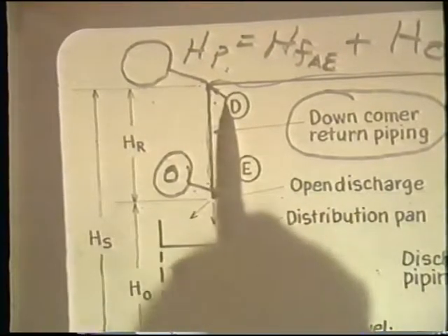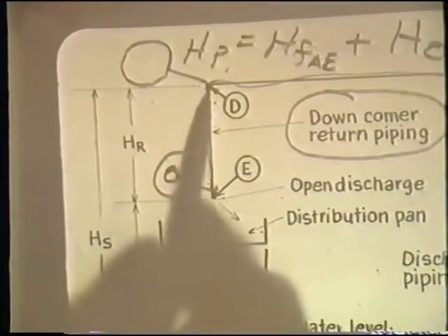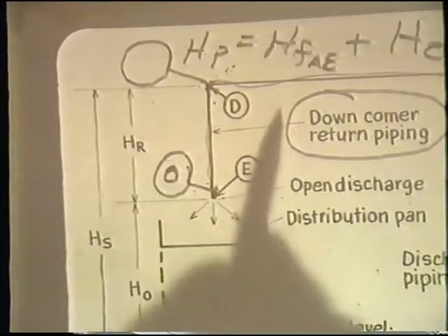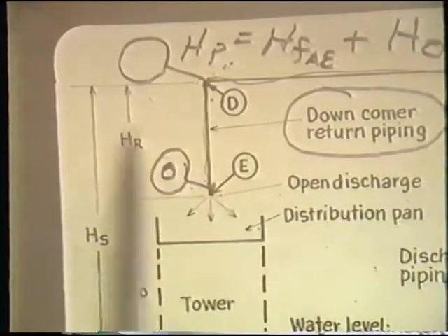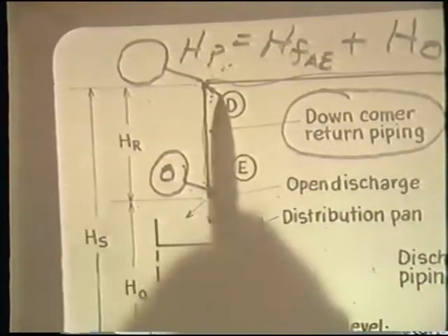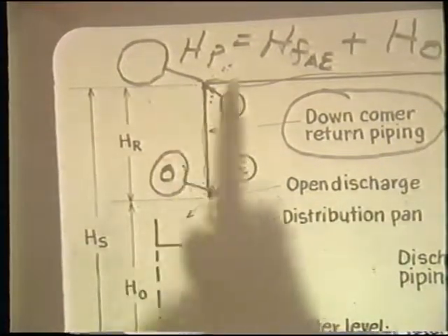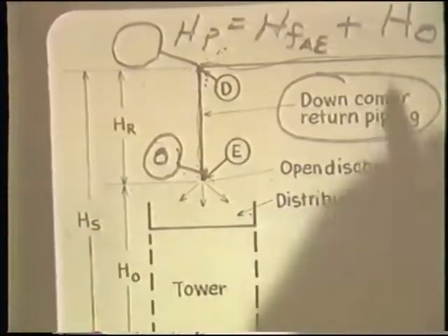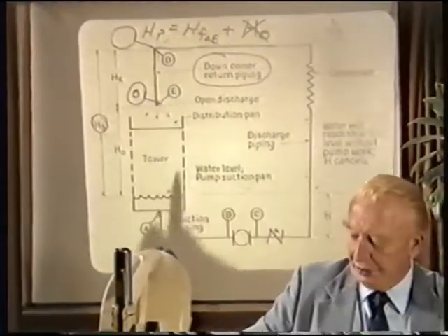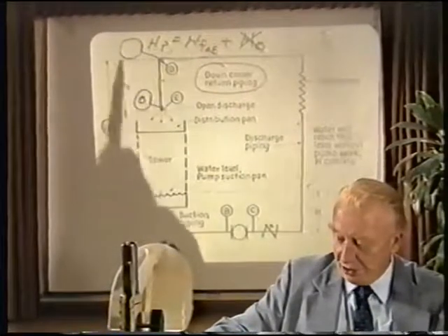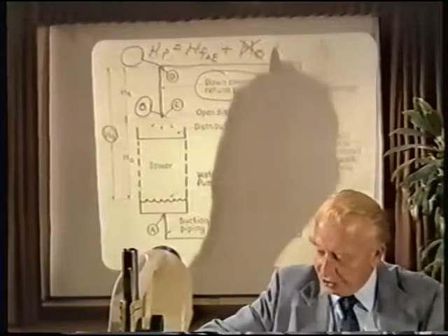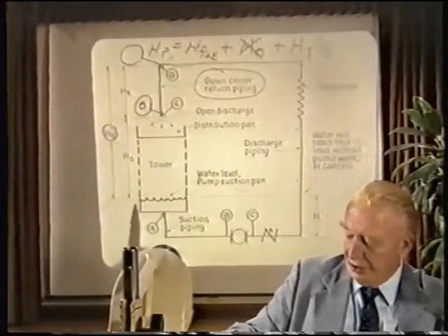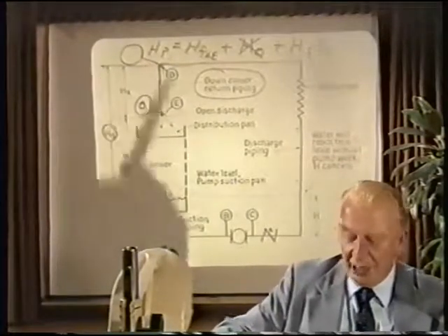Now, should a vent point occur at D, as caused by loose piping or by purposeful arrangement by placing a vent at this point, we will not establish the siphon draw. And because we have not established that siphon draw, we cannot cancel that part of the piping system in terms of the pump selection. And the pump head in this circumstance must become the total height of the piping system above the water level, in this circumstance H sub S, being from the water pan level to the top of the piping system.